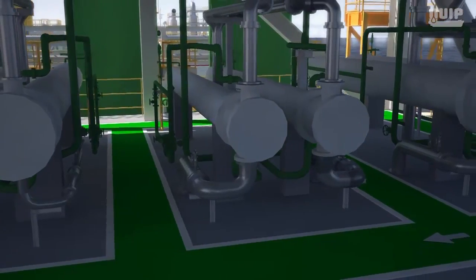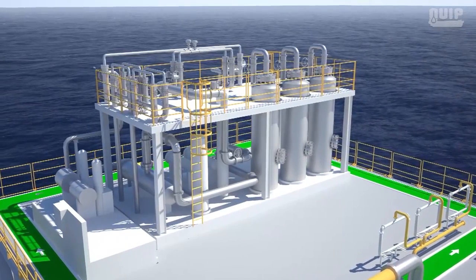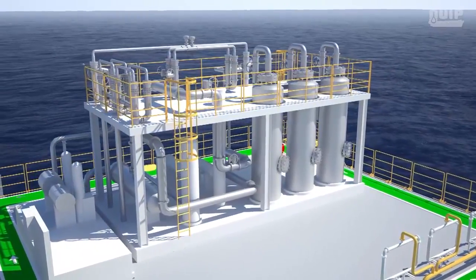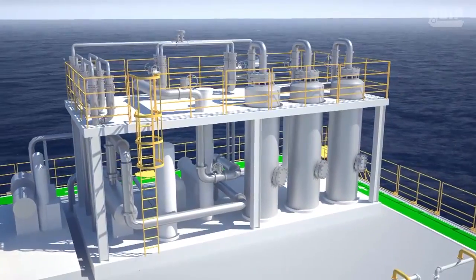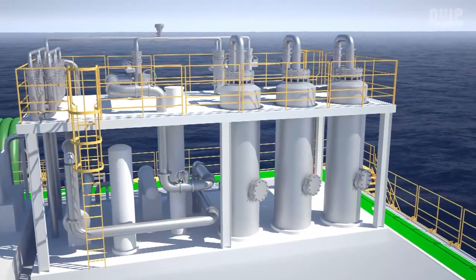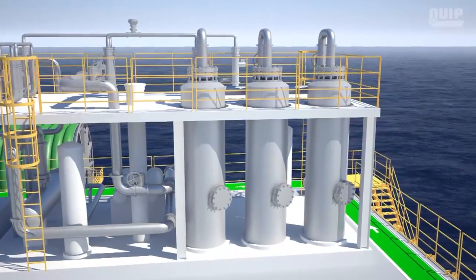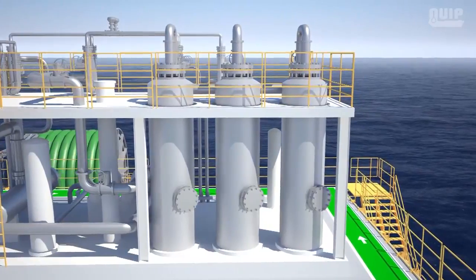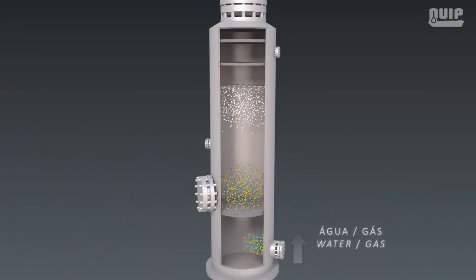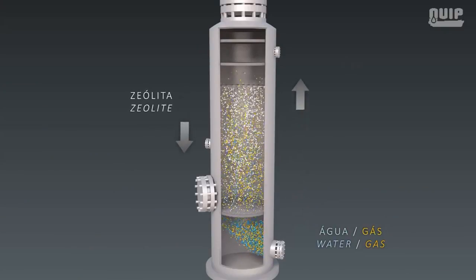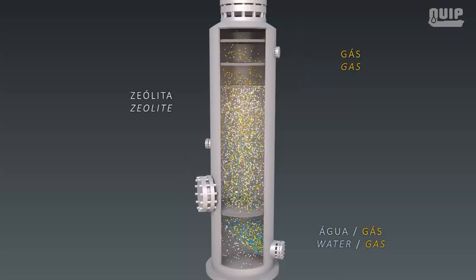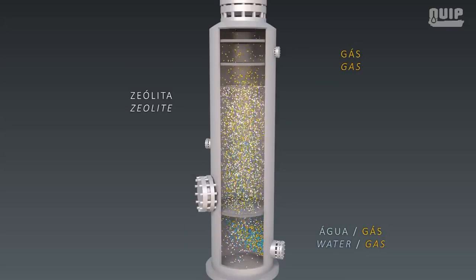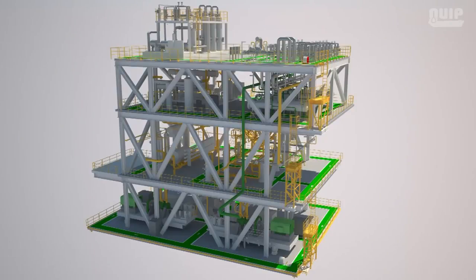The compressed gas then goes to a dehydration system that is composed of adsorption towers and filters that remove the humidity from the gas. The gas initially passes through coalescing filters to remove suspended particulate material. It then goes to the adsorption towers, which contain zeolite, a particulate material that retains humidity from the air. The dry gas is sent to another filter to remove any zeolite it may have picked up. At this point, part of the dry gas will be sent to the third main compression stage, and the rest will be sent to the fuel gas treatment system.